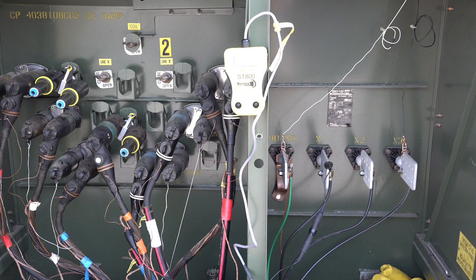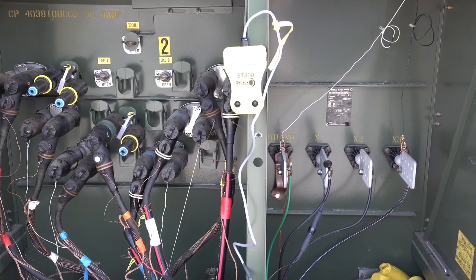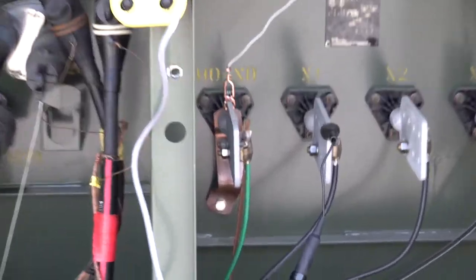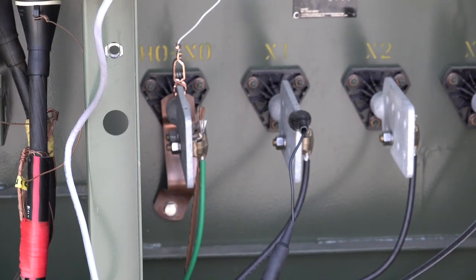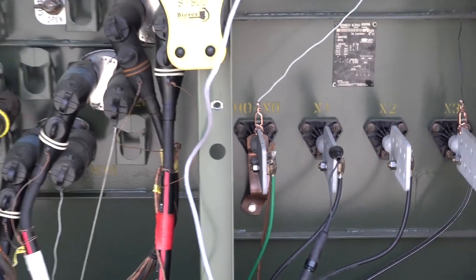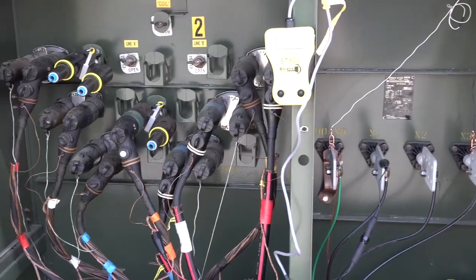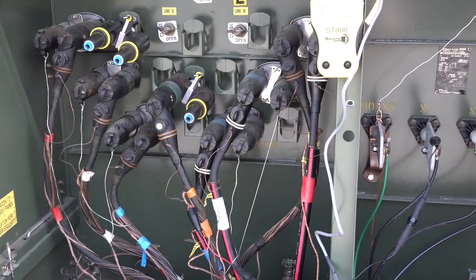Now we will demonstrate how to use the ST800 to identify primary energized or de-energized cable in a manhole or a ditch. Our first demonstration will be to use the ST800 on de-energized isolated primary cable with a secondary power source available. Notice how we have the ST800 black lead attached to the secondary power source and the red lead attached to the concentric of the de-energized isolated cable we want to identify.